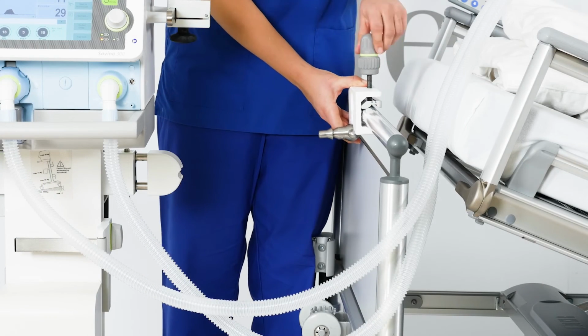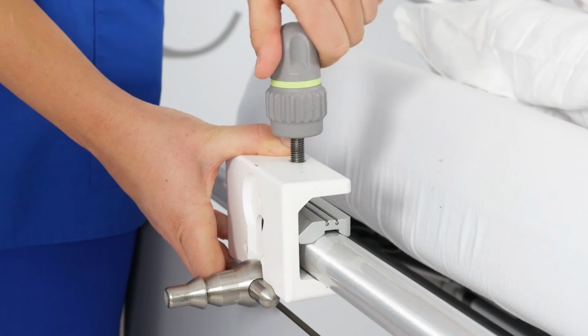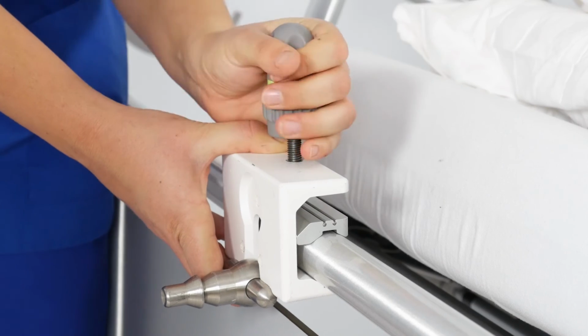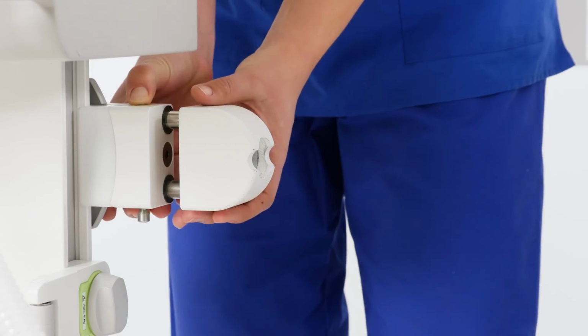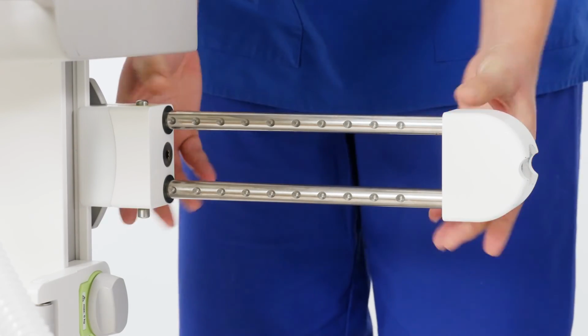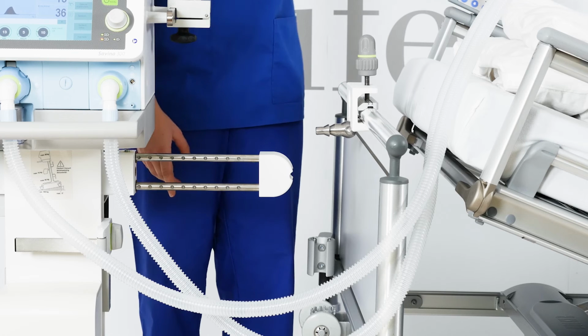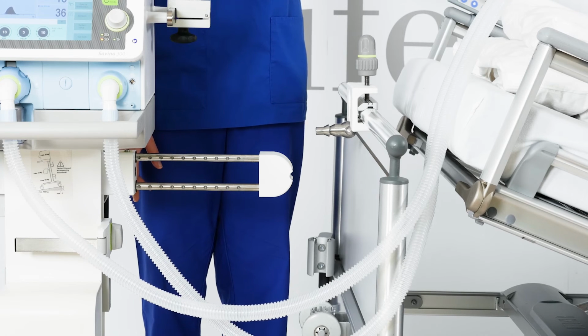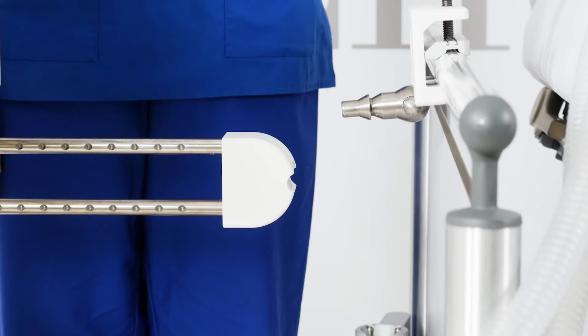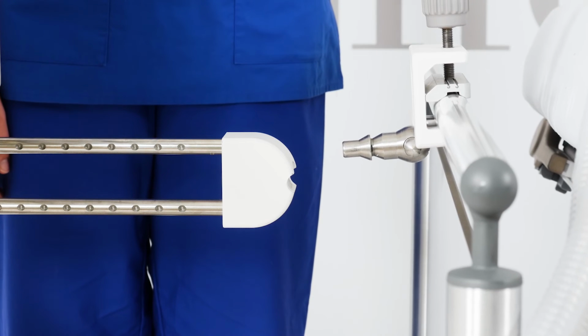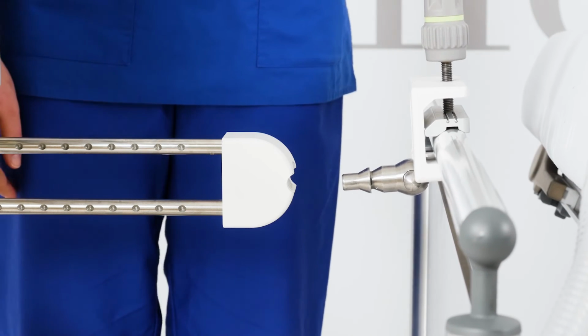Attach the bedside coupling part to the rail or to the bar at the head end of the bed and align the coupling connector horizontally. Then couple the device and the bed. To do so, lock the casters on the bed. Bring the device side coupling part and the bedside coupling part to the same height. Adjust the height of the bed or reposition the device side coupling part on the trolley column for this purpose.